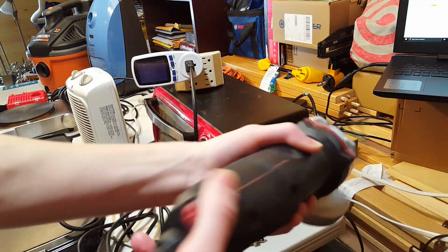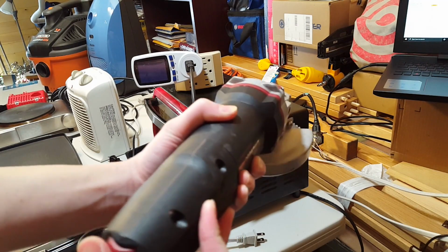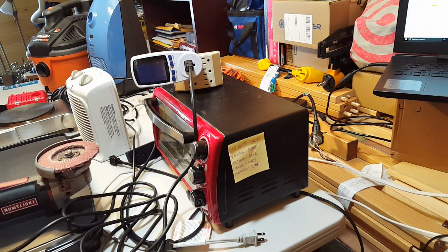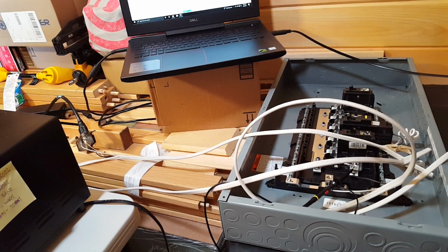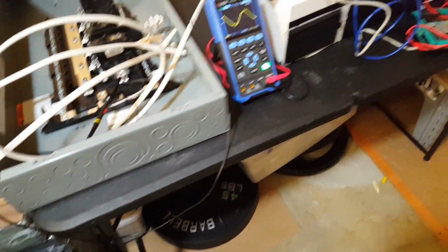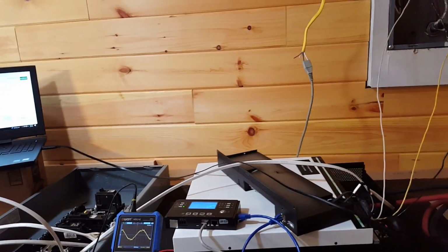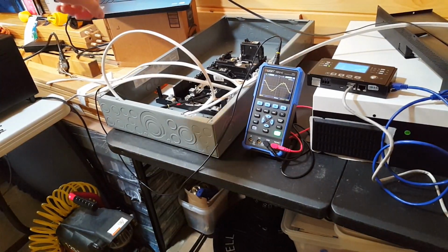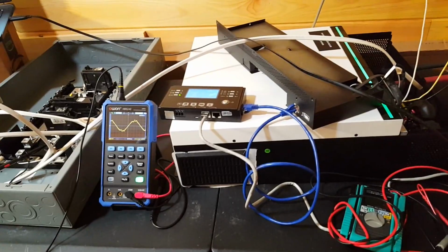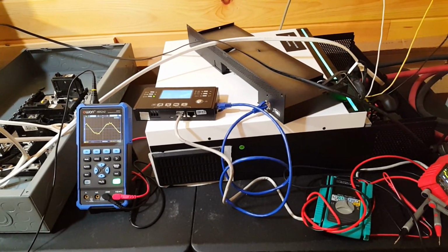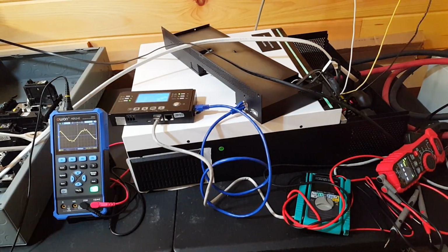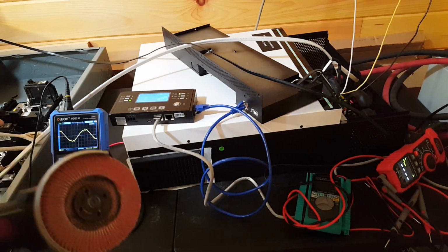Supposed to be 8 amp. It is variable speed. 6 is the high setting. Of course, we're going to do the high setting. We're back in battery mode. BMS has reset. We are going to check inrush. I'm going to need my tripod because I have to hold this on switch for the grinder, and I got to switch on the breaker, so I can't hold the camera. I'll just have to set the camera on the tripod. Try to get AC amps on video. Can I start an 8 amp grinder?